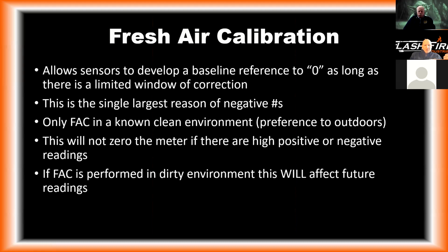Now with the Draeger meters, they do not fresh air cal on startup. I forget if this is in the PowerPoint, so I'm just going to say it now. They do not fresh air calibrate on startup. But when you start the meters up, they do require a 3 to 5 minute warm-up period before it will let you fresh air calibrate the meter.